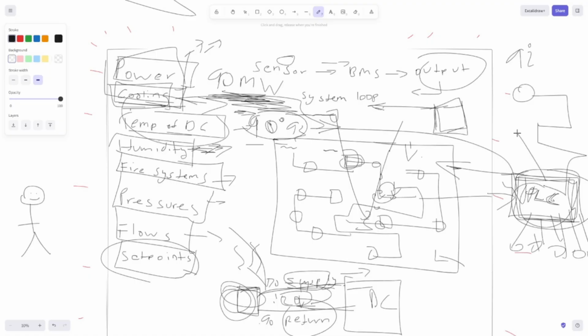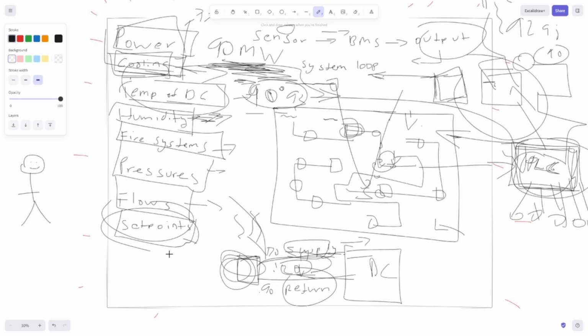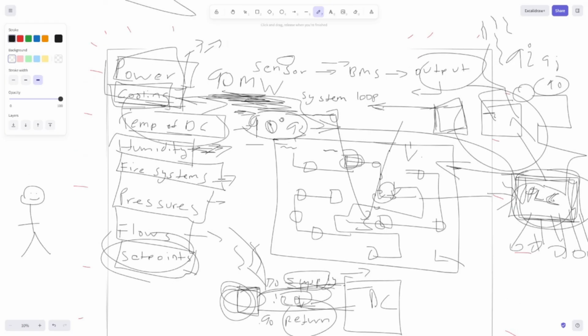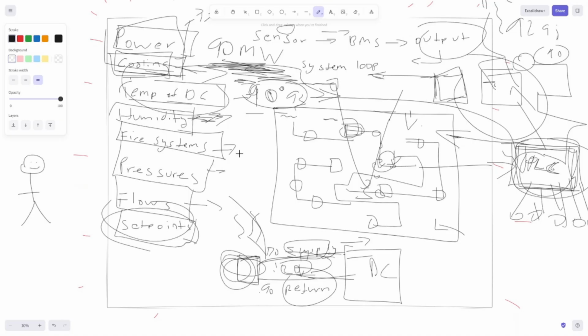Okay, then the PLC sends a command to a chiller. The chiller starts running, the chilled water gets cold, the data center drops to 91, then 90 degrees. After that happens, we've reached a set point, and then the chiller stops right there. And usually they're really good, especially in a really, really big data center. The set point is always reached, plus or minus whatever your tolerance is for wherever you're working. That is basically what a BMS does.